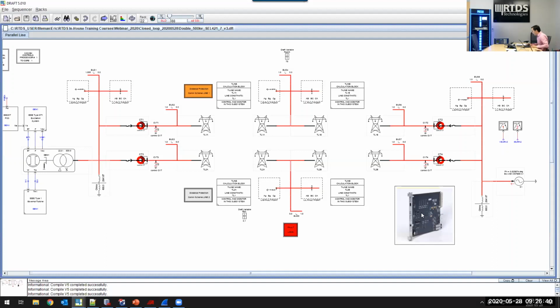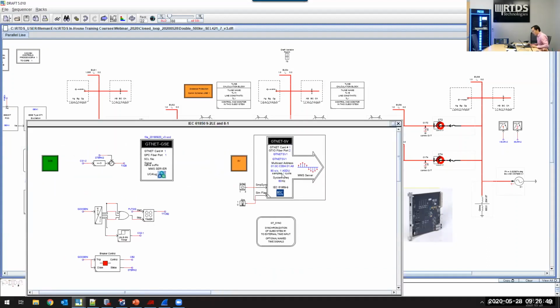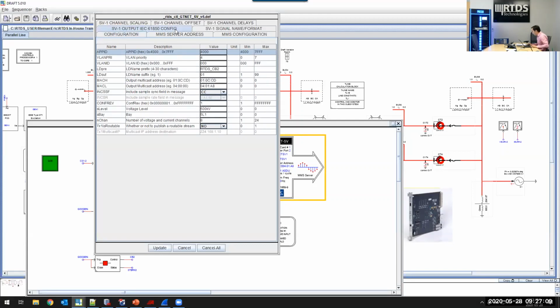So now let's have a look at the IEC 61850 interface that will be used for communicating with the physical relays. Let's start with the SV component. Now, the main function of the GTNet SV in this demo is to send voltages and currents at breaker 2, which is here, to the external relay using IEC 61850 sample value protocol. The key parameters associated with the IEC 61850 SV protocol, such as the SV ID, the destination MAC address, and more, are configured in this menu tab.